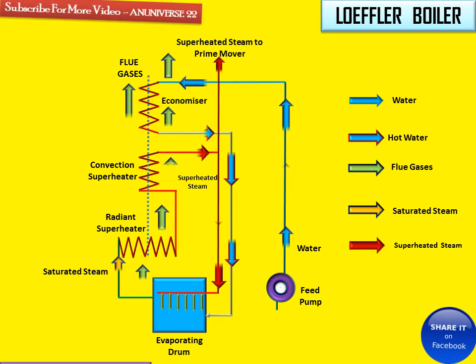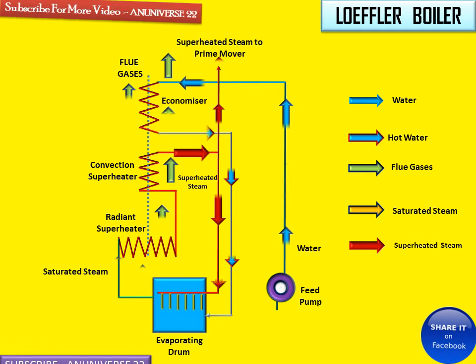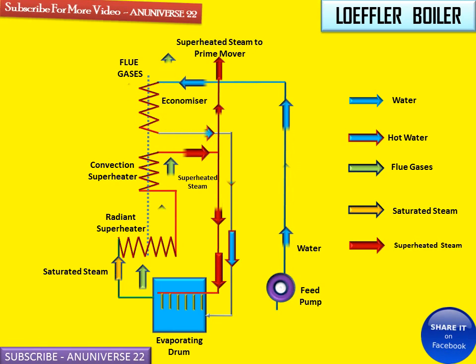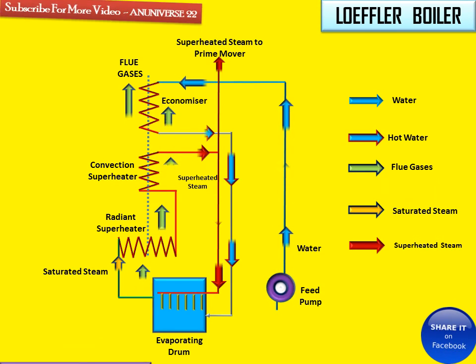This boiler can carry a higher salt concentration than any other type and is more compact than indirectly heated boilers having natural circulation, making it well suited for land or sea transport power generation. Loeffler boilers with a generating capacity of 100 tons per hour operating at 140 bar have already been commissioned. Today we learned about the main components of the Loeffler boiler, their working, and how water is converted into superheated steam.